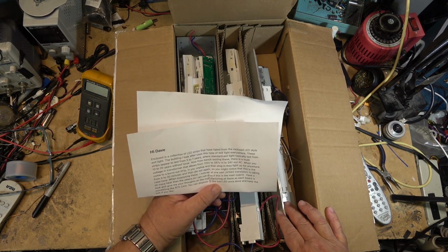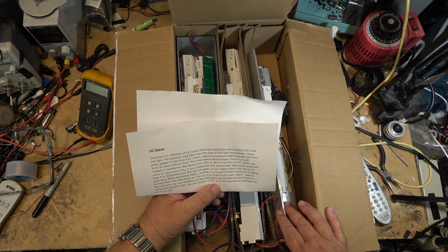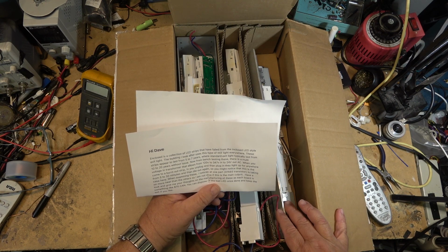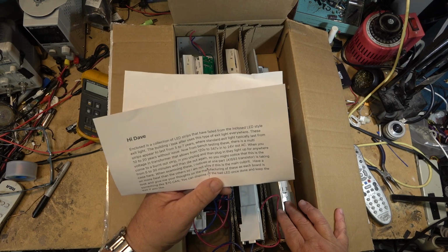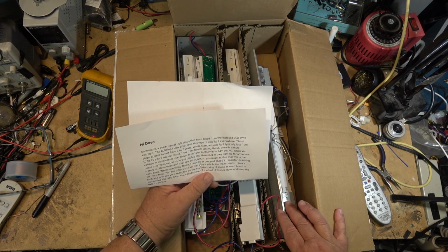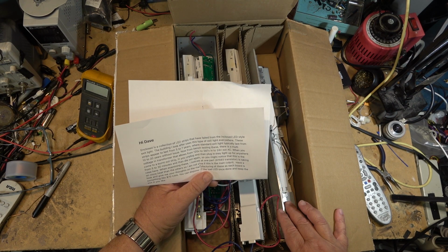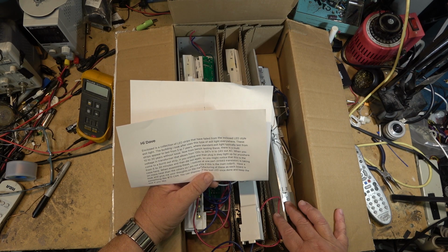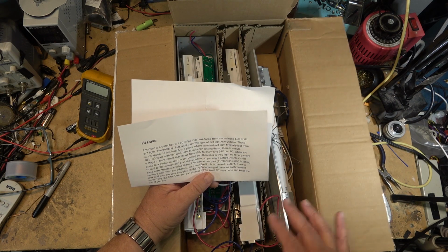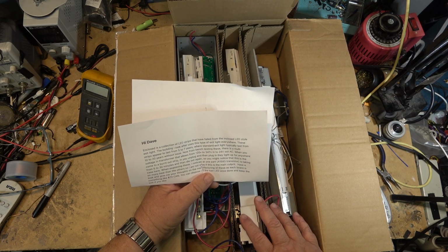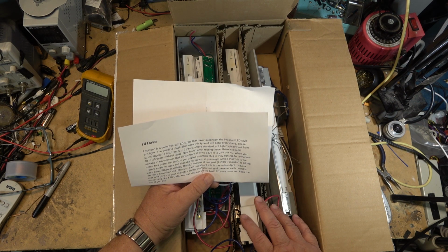The building I look after uses these type of exit light everywhere. These strips appear to last 5 to 7 years, where the old standard exit light typically lasted 10 to 20 years without issue. From bench testing, there's a transformer that allows 120 to 347 volts in and 24 AC out. When you come to a burnt strip, if you unplug and plug it back in, they light up anywhere from 5 to 30 minutes and then die out again. You might notice that's the case here.